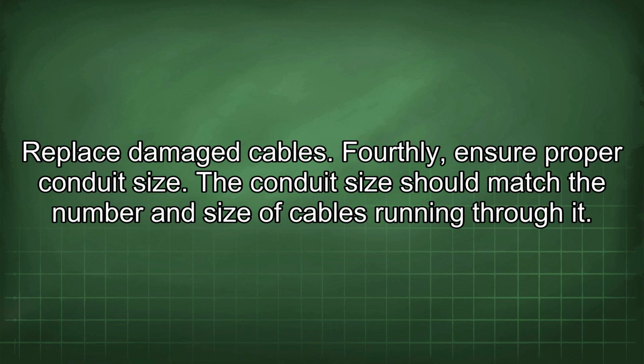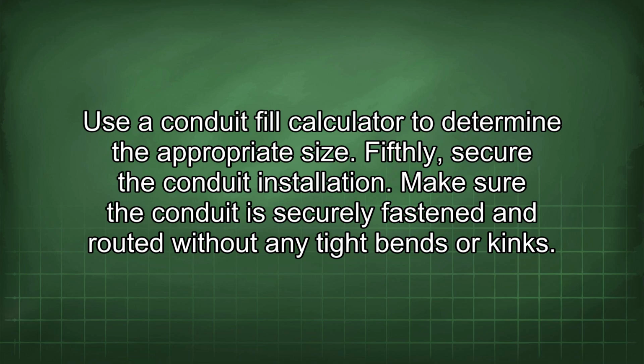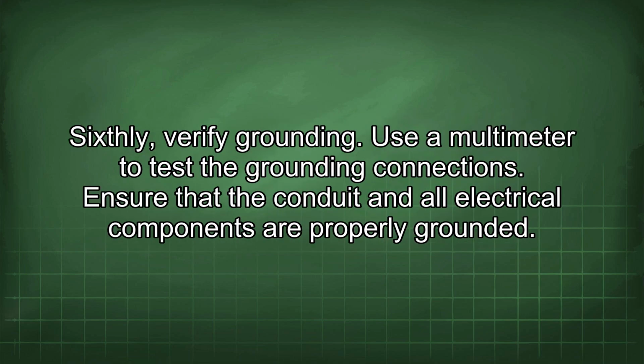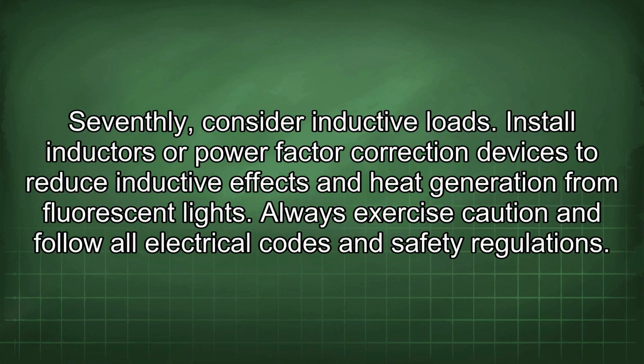The conduit size should match the number and size of cables running through it. Use a conduit fill calculator to determine the appropriate size. Fifthly, secure the conduit installation. Make sure the conduit is securely fastened and routed without any tight bends or kinks. Sixthly, verify grounding. Use a multimeter to test the grounding connections. Ensure that the conduit and all electrical components are properly grounded. Seventhly, consider inductive loads. Install inductors or power factor correction devices to reduce inductive effects and heat generation from fluorescent lights. Always exercise caution and follow all electrical codes and safety regulations.